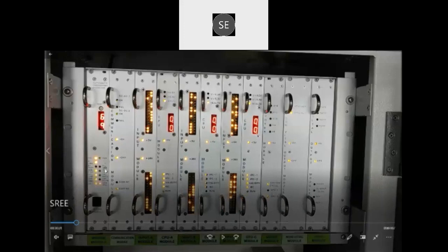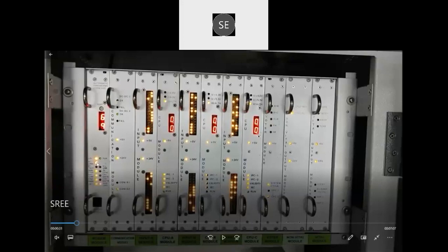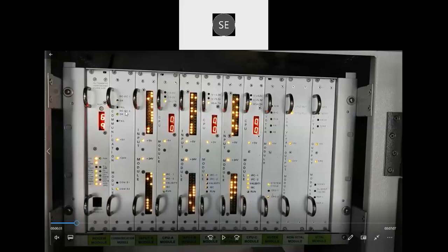The bottom channel is the even channel. Here we can see the power supply, even status, even health, and everything. So now it is connected between an odd channel and an even channel. And the second is the communication card. Here it is providing power supply. You can see that DC-DC converter 1 is okay and DC-DC converter 2 is okay. And there are two redundant DC-DC converters so that in case one fails, the system will continue working with the other DC-DC converter.